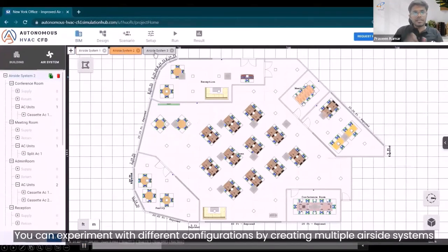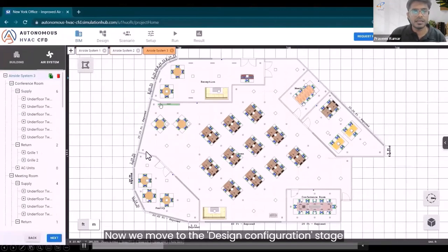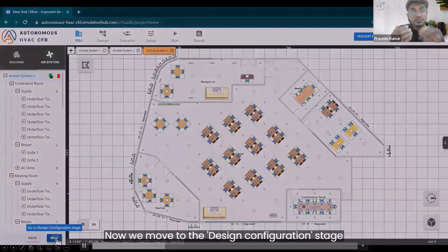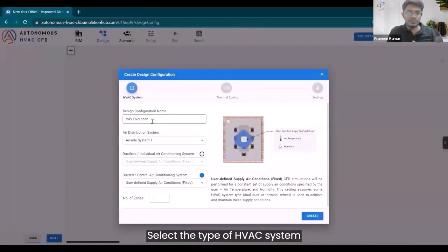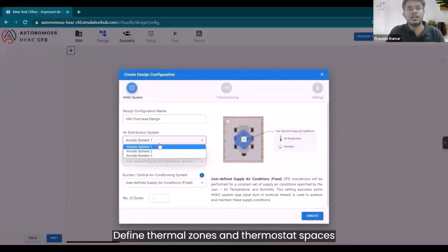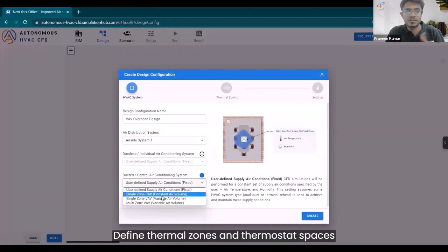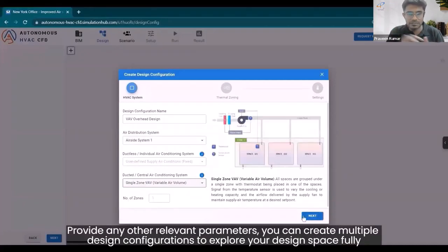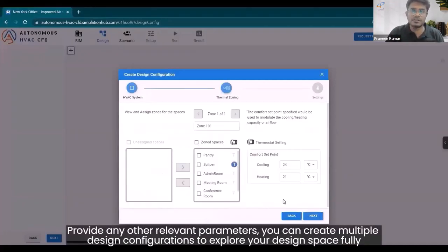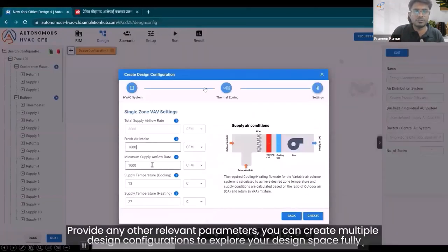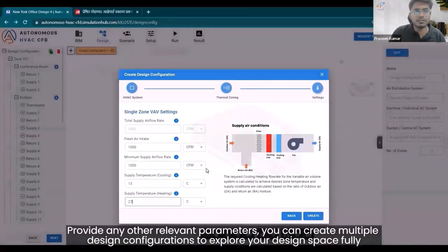So you can create multiple airside systems and move on to the design configurations, where you specify whether your system is a CAV system or VAV system. You can also set multi-zone or single zones, arrange these spaces to provide zoning, and set the thermostat to the space which is governing the system. So the design configuration is done.